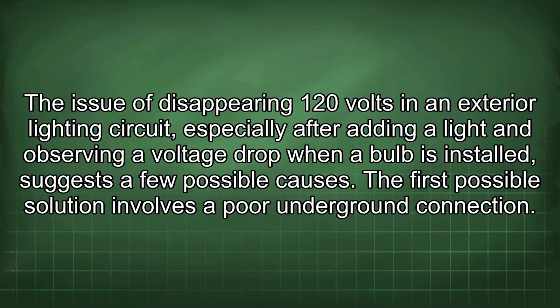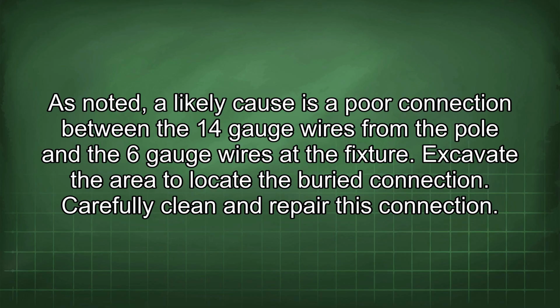The issue of disappearing 120 volts in an exterior lighting circuit, especially after adding a light and observing a voltage drop when a bulb is installed, suggests a few possible causes. The first possible solution involves a poor underground connection. As noted, a likely cause is a poor connection between the 14-gauge wires from the pole and the 6-gauge wires at the fixture. Excavate the area to locate the buried connection.